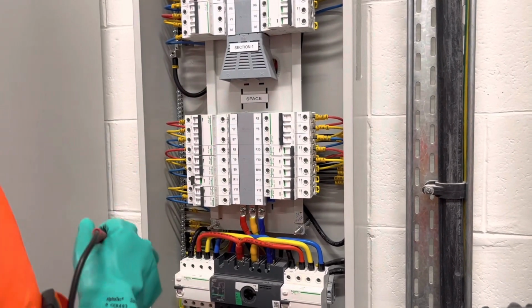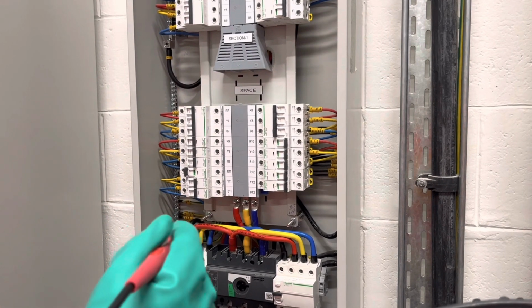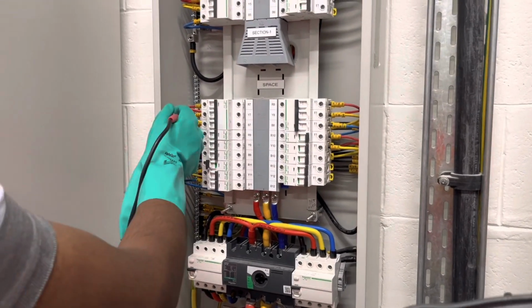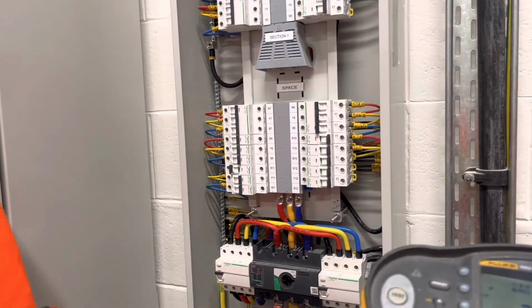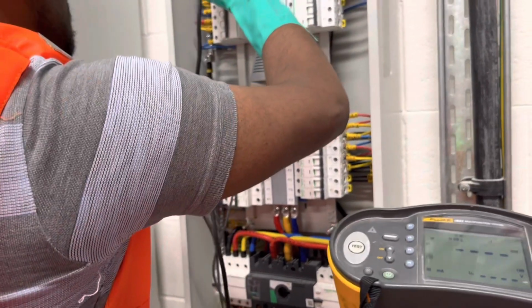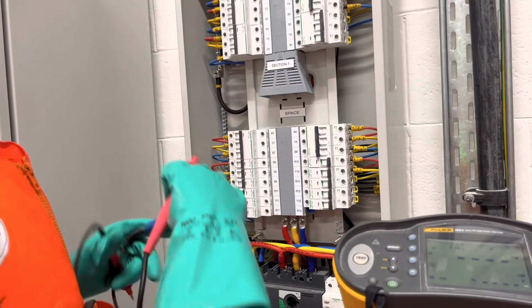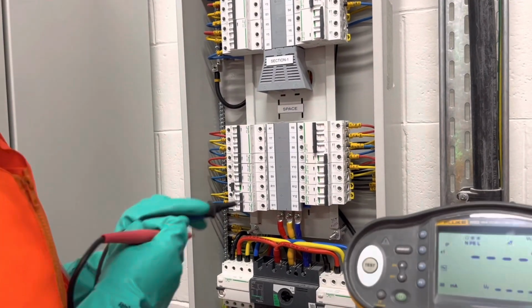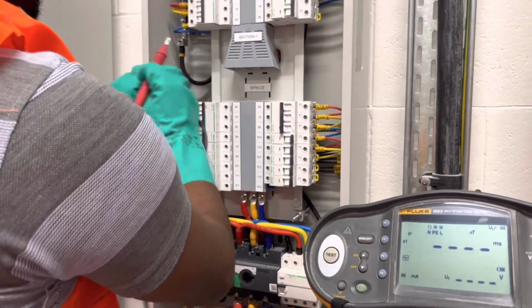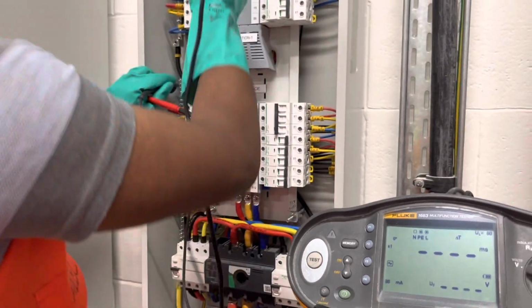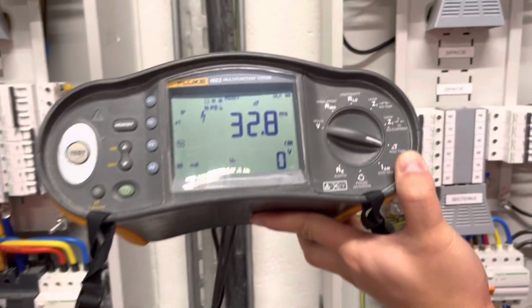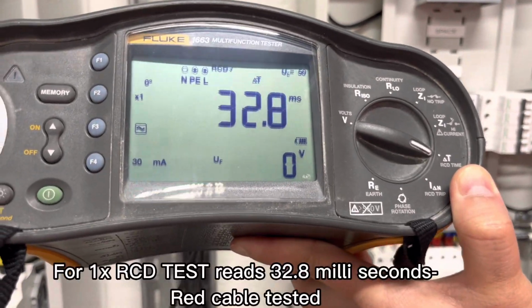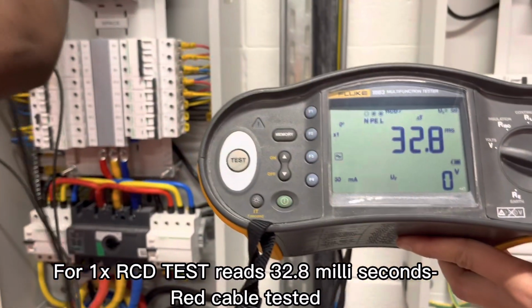Okay, where are we now? Same breaker. So, live? Trip. Live and neutral only? No, live and earth only. No need for neutral. Neutral is not required, right? So, live and earth bar. How much? Okay, 32.8 in times 1, no? The yellow one, okay.